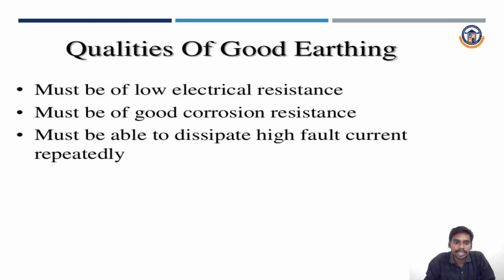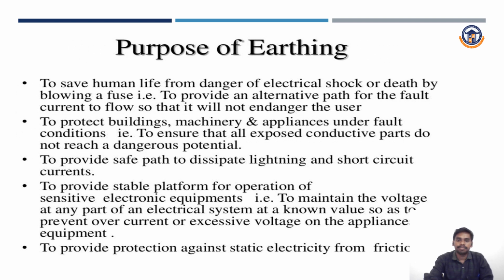Qualities of good earthing: it must have low electrical resistance. As said before, the low resistance path will be chosen by the current. It must have good corrosion resistance. It must be able to dissipate high fault current repeatedly. Purpose of earthing: to save human life from the danger of electric shock or death by blowing the fuse.